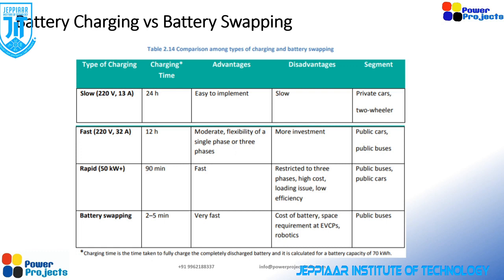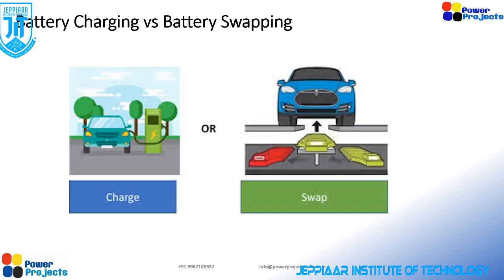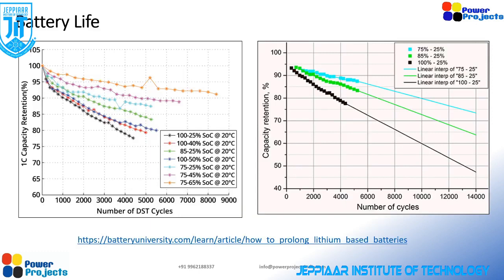The best lithium ion battery which is available is a 6C battery, that will be able to charge your battery in 10 minutes. Minimum it will take 10 minutes, but that will be in the range of about $600 per kilowatt hour, compared to about $200 per kilowatt hour for a 0.5C battery, and probably a 2C battery will be in the range of about $280 to $300 per kilowatt hour, right? And there are quite a lot of questions with respect to the battery life.